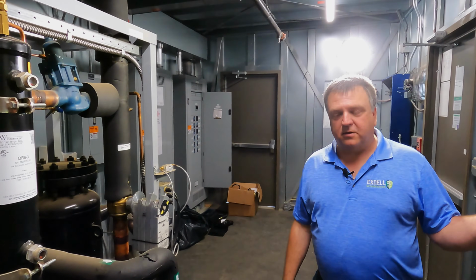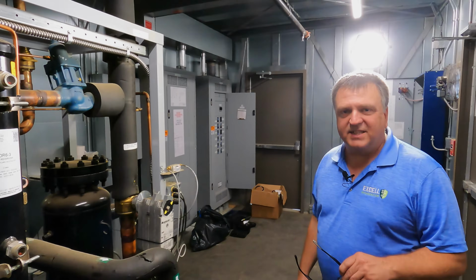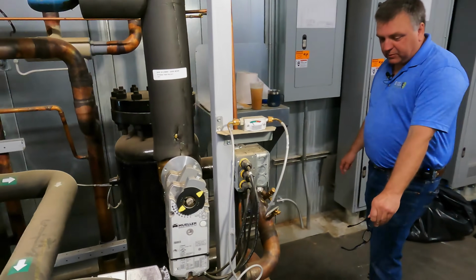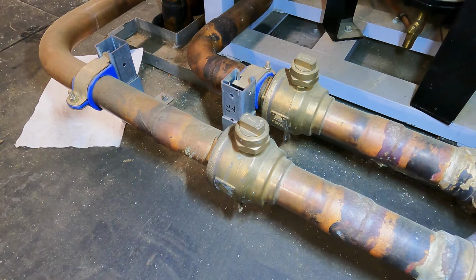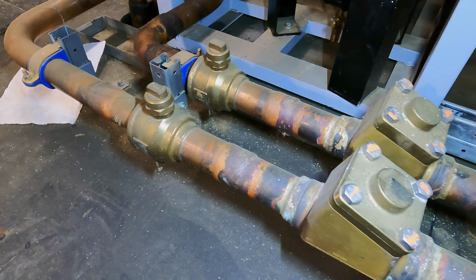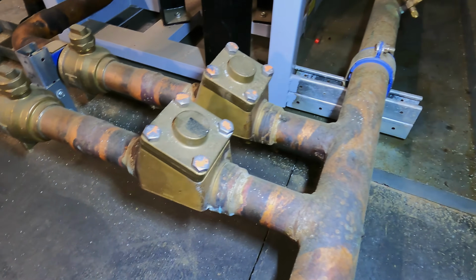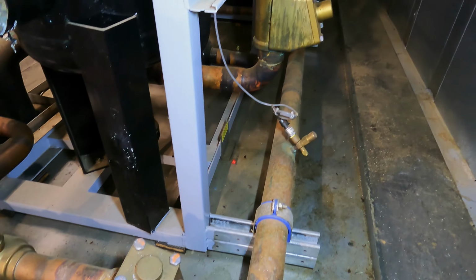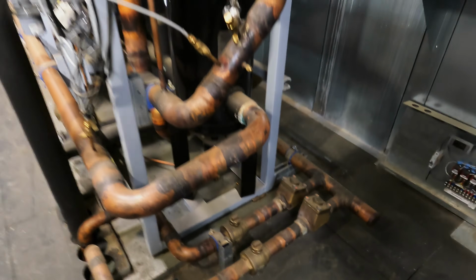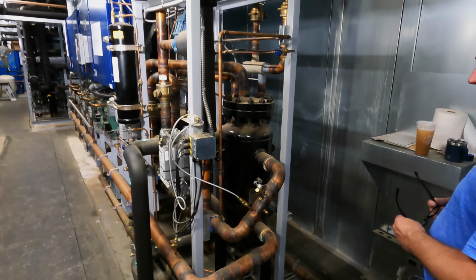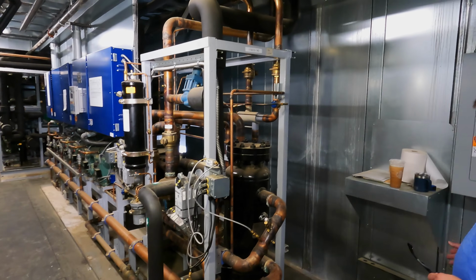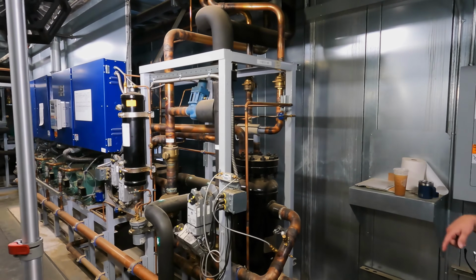We've left the condenser, we're coming back into the motor room as a liquid state. Here are our liquid lines coming from the condensers. We have 2 check valves because when we have a low ambient condition, we're splitting the condenser in half, and we're going to pump the other half out. When we're pumping it out, we don't want that liquid to go back out into the condenser.